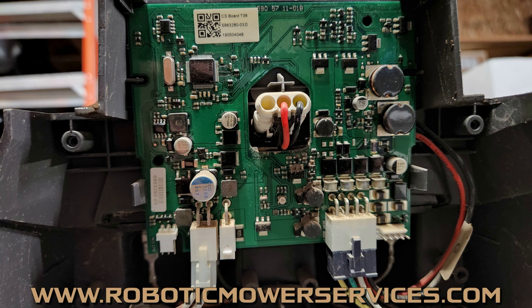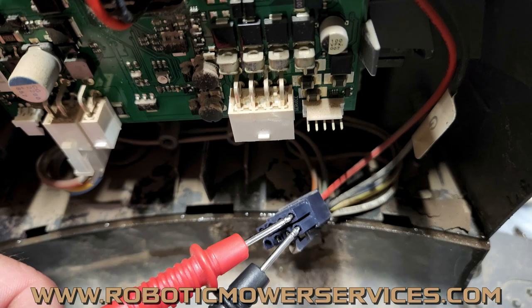As far as those two components, 90% of the time, if there's an issue with the transformer, you're going to see a voltage drop. So check the voltage at the plug for the low voltage cable on your transformer, and if it's putting out the 28 volts, plug your low voltage cable into it, then go back to your charging station board where you have that plug at the bottom, unplug it, and test the power coming through your charging station and everything.